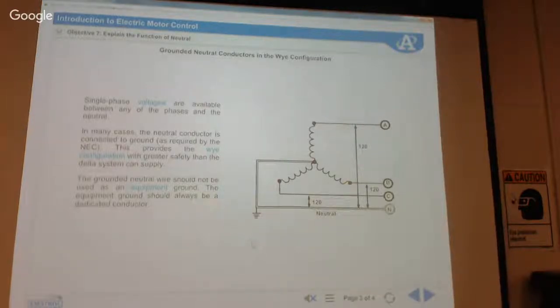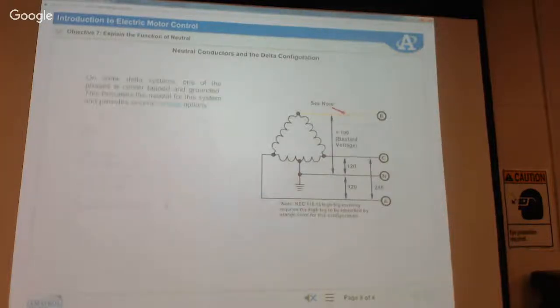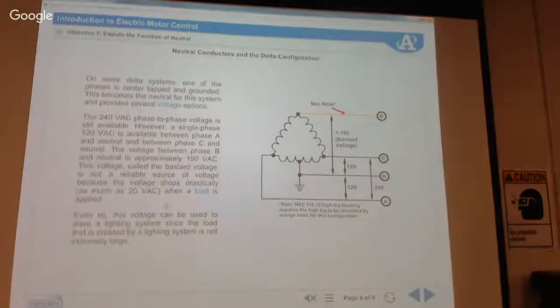They're saying you should bond your equipment to the physical ground, the frame of the building or something like that. Everything's going to go there, but they're saying don't use this. This is a neutral wire. So this is grounded here, and we can ground stuff past the ground point, but this is dedicated here because current's going to flow through these phases back to ground. So we shouldn't use that for equipment bonding. That's the white wire, neutral.